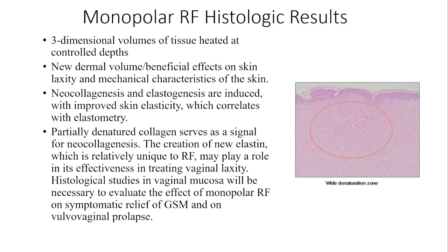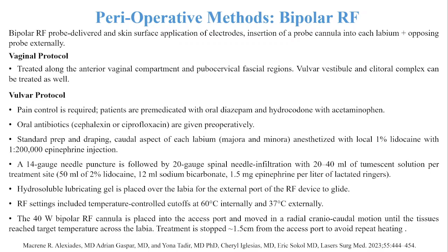Bipolar RF also exists, where there is a probe that is inserted and then an opposing probe that is applied externally. This is another technology. This one is painful, and pain control is required. This is a more aggressive procedure. Oral antibiotics are given preoperatively in this instance, and it's done by sterile procedure. So this is the bipolar method, and the cannula is placed into the access port and moved in a radial craniocaudal motion until the tissues reach target temperature. They look at 60 degrees internally and 37 external.